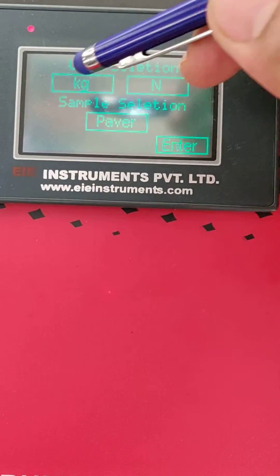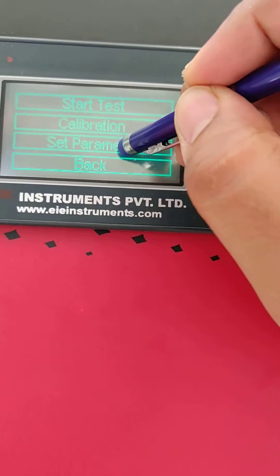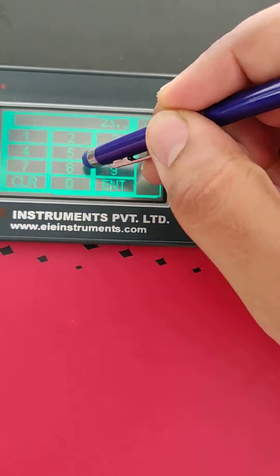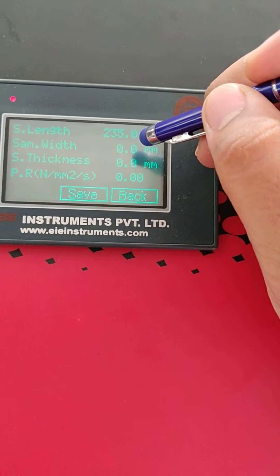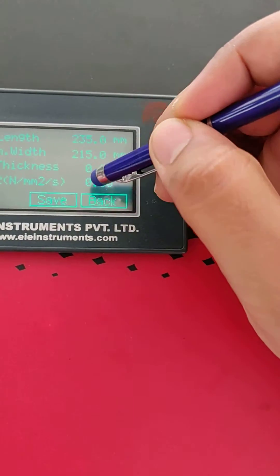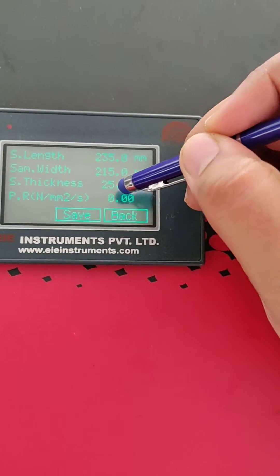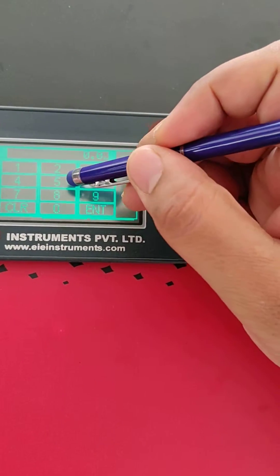We have to select the unit — here we are selecting kg, and our sample type is paver. After that, press enter to set the parameters. The length is 235mm. The span length is the width between the two rollers, so we keep 10mm on both sides, making it 20mm less — that is 215mm. Thickness is 25mm, and the pace rate, which can be set from 1 to 10, is set at 5.